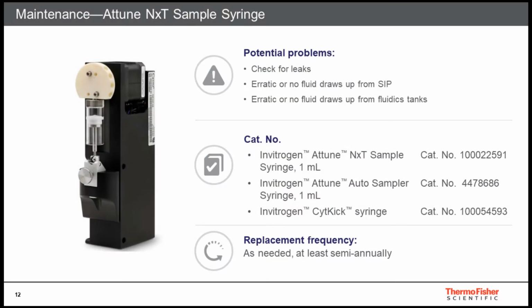Let's take a minute to talk about changing the syringes in the system. About twice a year, we recommend changing the syringe on the Attune NxT Flow Cytometer and the Autosampler. Depending on the type of autosampler present, the process may be slightly different, and we will talk more in detail about specific autosamplers. These syringes can be ordered from Thermo Fisher Scientific's website. In case of any issues, or in case the instrument is used heavily, frequent change of the syringes is recommended in order to best avoid any downtime. Please consult your local engineer or application specialist for guidance.